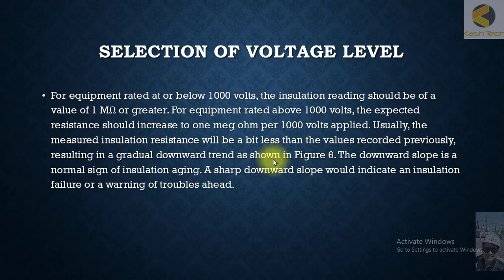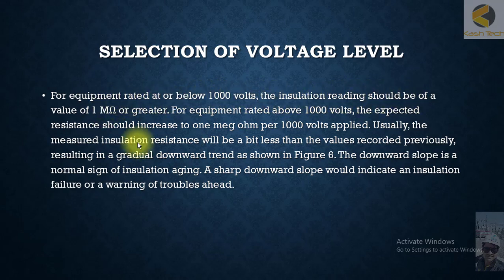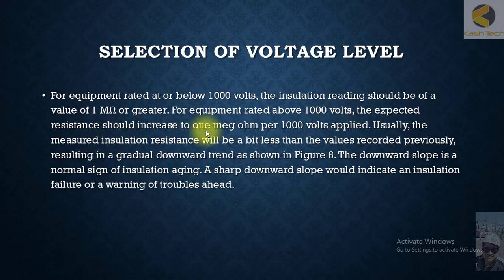We will discuss selection of voltages for maintenance testing. For equipment rated at or below 1 kV, the insulation reading should be 1 megaohm or greater. For equipment rated above 1000 volts, the expected resistance should increase to 1 megaohm per 1000 applied volts.